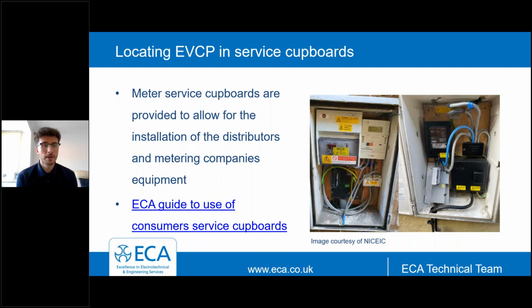And we have seen many examples where EV charging equipment and additional termination blocks have been added to meter service cupboards to allow for the additional equipment. It's worth pointing out that meter service cupboards are provided to allow for the installation of distributors' and metering companies' equipment. So ECA would advise against locating equipment in this location, as it could cause problems in the future where distributors and meter providers look to maintain their equipment, or they may look to upgrade their equipment.